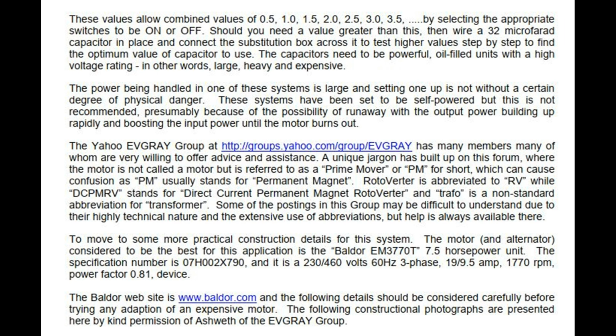These values allow combined values of 0.5, 1.0, 1.5, 2.0, 2.5, 3.0, 3.5, by selecting the appropriate switches to be on or off. Should you need a value greater than this, then wire a 32 microfarad capacitor in place and connect the substitution box across it to test higher values step by step to find the optimum value of capacitor to use. The capacitors need to be powerful, oil-filled units with a high voltage rating, in other words, large, heavy and expensive. The power being handled in one of these systems is large and setting one up is not without a certain degree of physical danger.